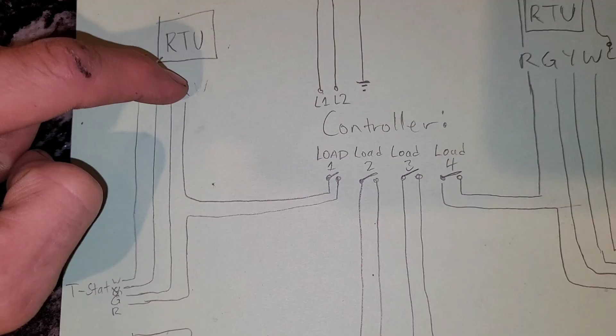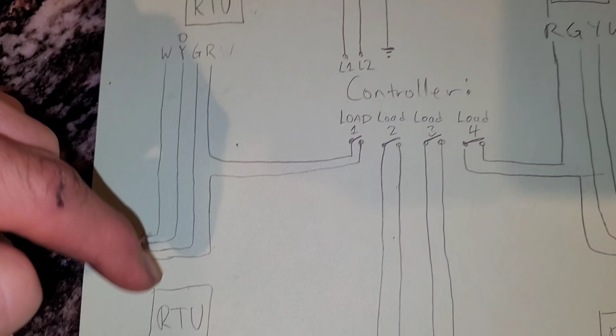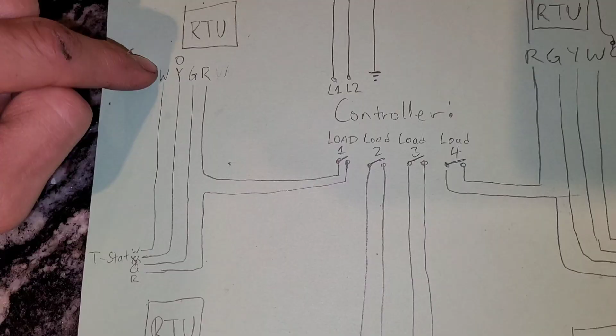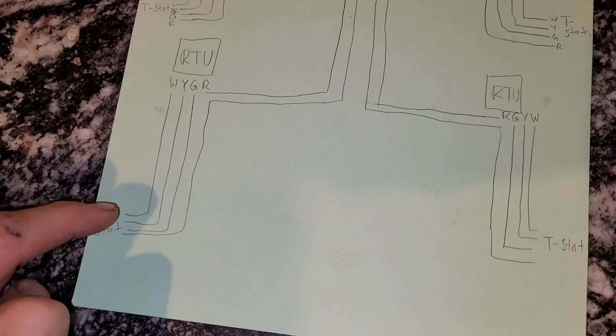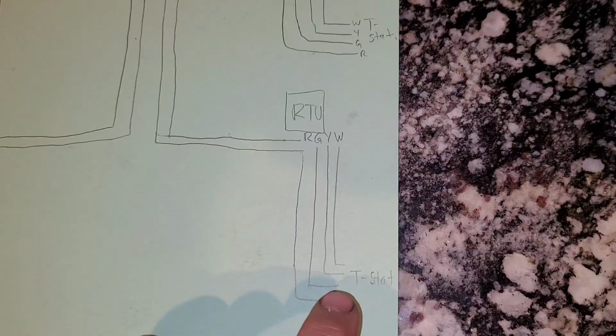So from each rooftop unit we have the R wire going down to the controller, and then if the controller has that on, it sends it down to the thermostat, and then the thermostat is able to send it up on any one of the calls. If it sends it on the W, you get heat, Y, you get cooling, G, you get fan, and that is the same for all the rooftop units. So the controller is just interrupting the 24 volts going from the rooftop unit to the thermostat because it prevents it from bringing on any single call.